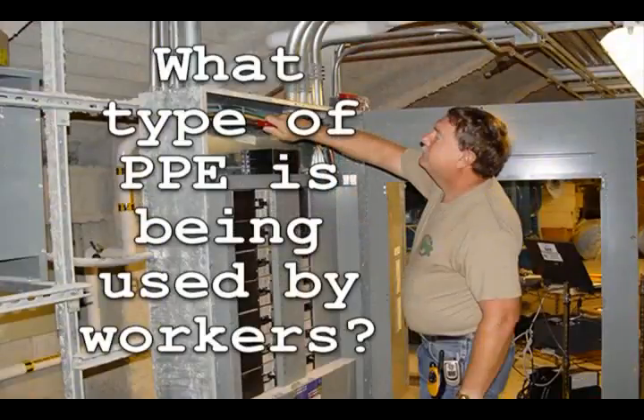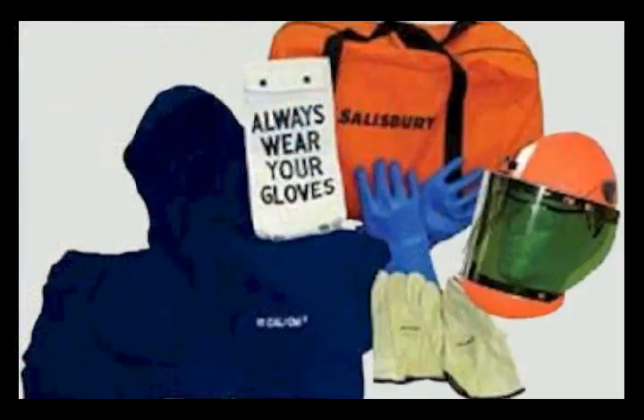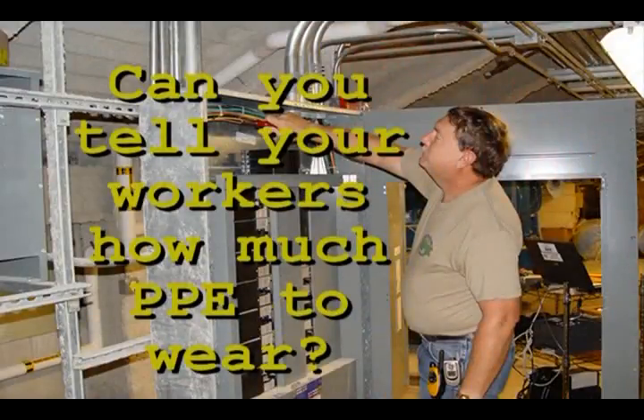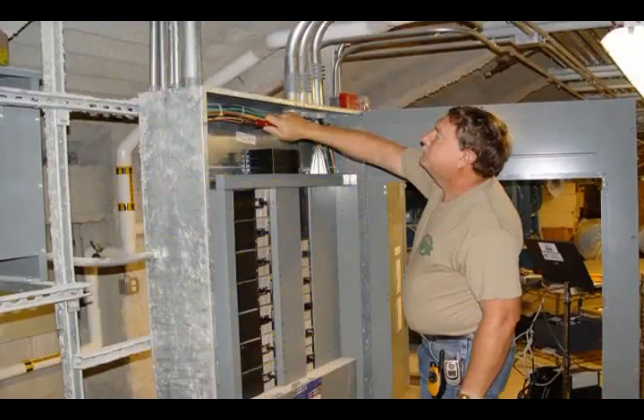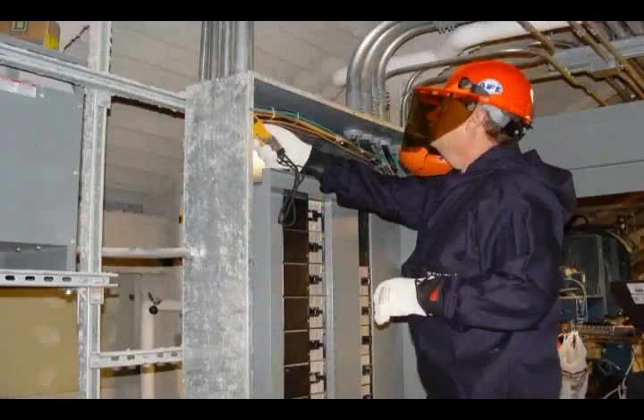First, let's look at a few common sense issues. Take a look at what type of personal protection equipment, or PPE, that your service or maintenance workers use when working around electrical equipment. Did they use approved rubber gloves, fire retardant clothing, eye or face protection? Do you have any idea of the dangerous levels of current in each panel that your workers maintain? Let's take a look. This worker is in grave danger. While it may not look like it, that electrical panel has over 50,000 amps of current potential should an accidental short occur. An arc flash survey provided that information, and the arc flash warning label informed the worker of what type of personal protection equipment to use and wear.